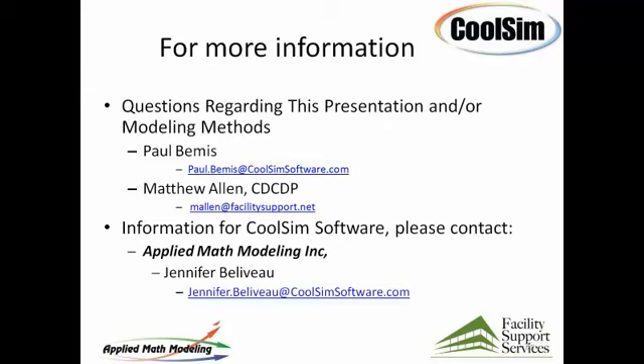So the first one is, what does the process for gathering and uploading all the data look like? He's looking for key activities and time frames. And that's to you, Matt, I guess. Yeah, in this particular data center with 5 CRAC units, all the information can be gathered in approximately one full day, and that's capturing all the PDU information and the supply and return temperatures and all the CFD, or CFM, I'm sorry. So all the technical data can be captured in one day for a room this size.